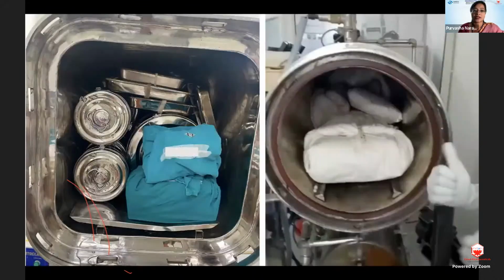This is the view of our autoclave system, where we have trained technicians taking care of all these processes. On your left, you see a very heavily packed autoclave, the steam sterilizer, which has been very densely packed, whereas on the right is the right way to set the instruments inside, and it should be loose enough to allow the steam to pass through the sets. The heavier ones are placed at the bottom and the lighter sets are placed on top.